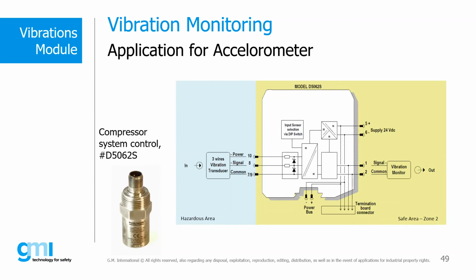Transducers for measuring acceleration and vibration are increasingly used in the mechanical and structural field, vehicle testing, industrial monitoring, predictive maintenance, benches and rooms test, aerospace experimentation, and so on. When these accelerometers operate in a classified area, they must be isolated through an intrinsically safe barrier. As in the slide, the D5062S isolates this particular type of sensor, transparently providing the reading system placed in the safe area with a waveform of the same level and frequency as that generated by the sensor, so that the system can read the signal correctly.